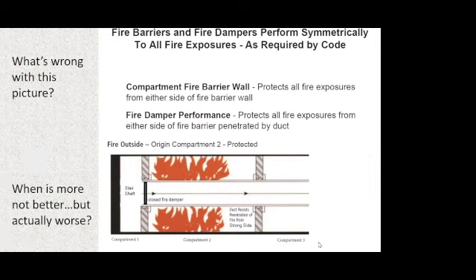So we have an HVAC system that's dedicated to protecting this exit stairwell. And what we unfortunately see is what I call the most common design to failure scenario that's out there. I say design to failure because they used one of the more common fire rated duct configurations, and in so doing, they needed to provide a fire damper at the penetration of the stair shaft fire barrier. This is a classic case of more is not better. What we have here is a fire damper which is going to close, and when it closes, it interrupts our smoke control system. And this is actually prohibited by the code.